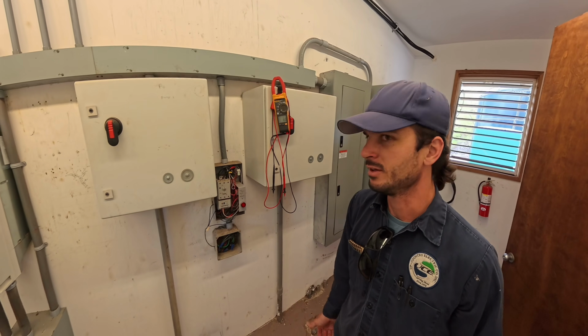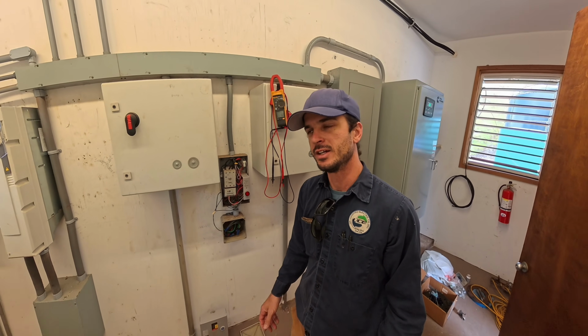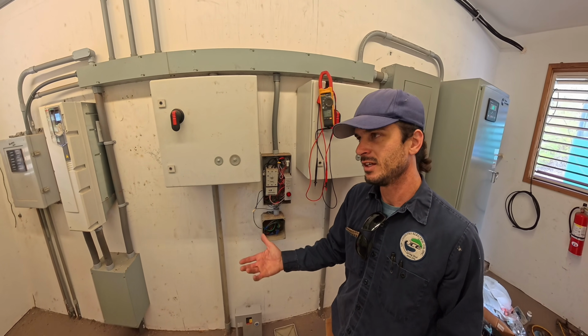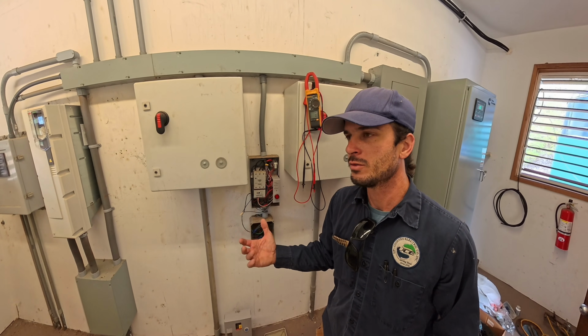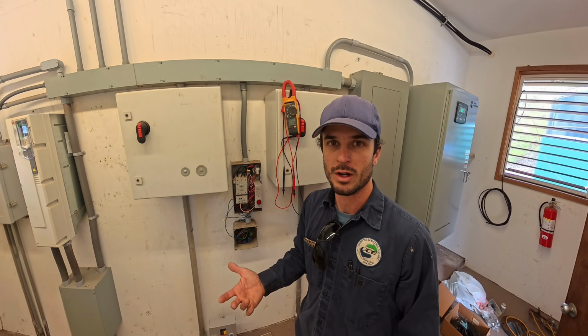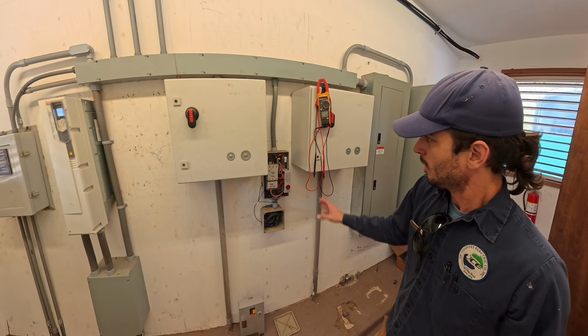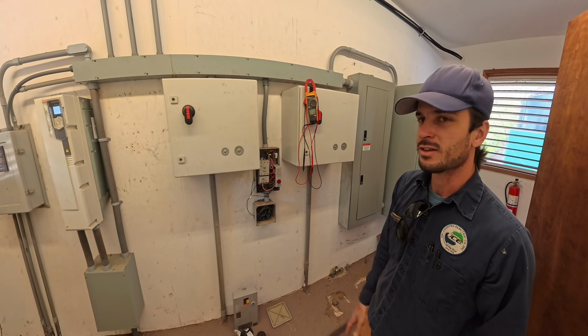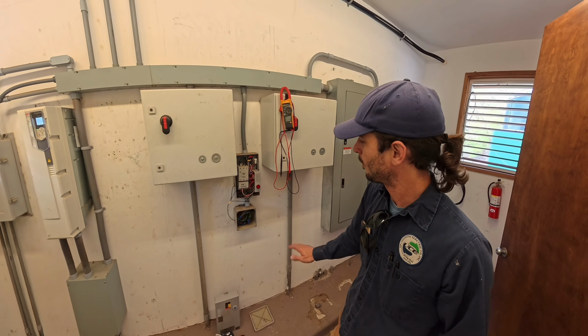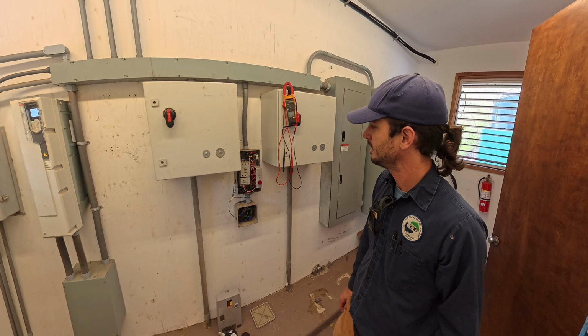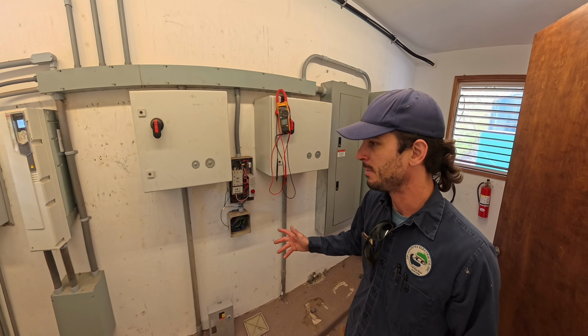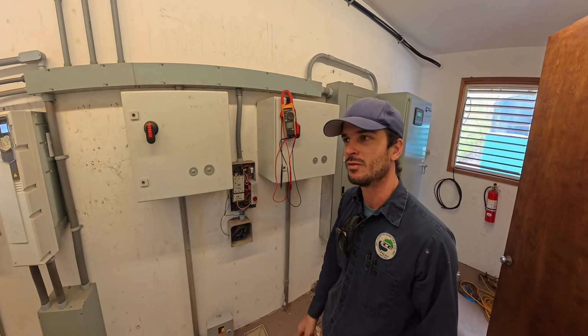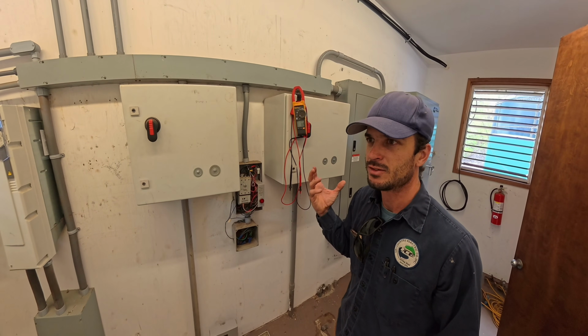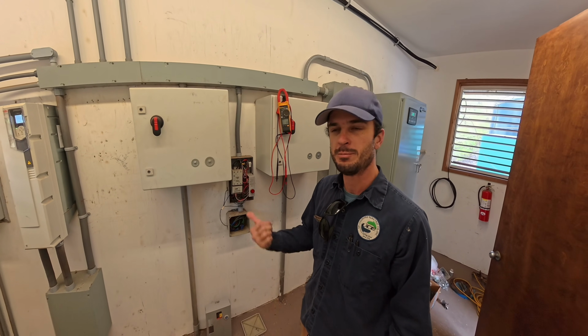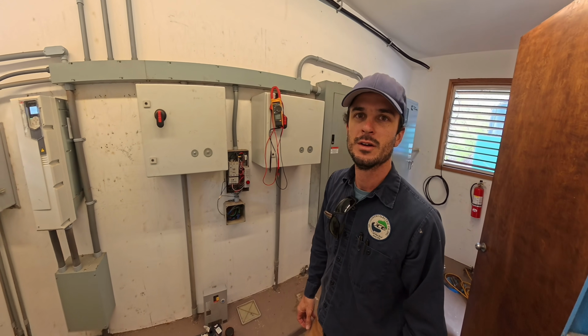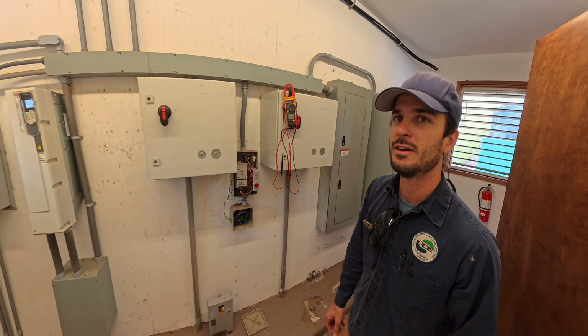What they'd like though is if we could tie it into their fancy SCADA so that they can see the status of the float switch and reset the pump and run it remotely. So we're going to kind of dig through the existing wiring here as best we can. Hopefully it's just a simple change, and try to make it so the SCADA sees the position of the float and decides to start and stop the pump on its own based on that float switch input. All right, let's start digging into the wiring.